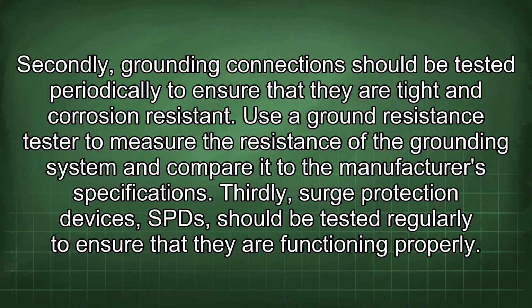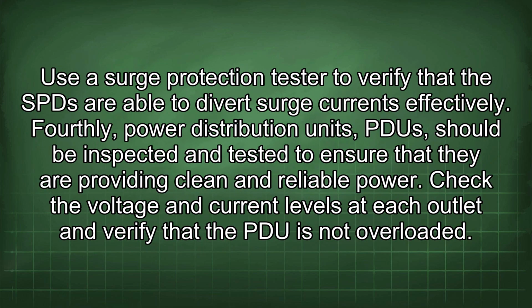Secondly, grounding connections should be tested periodically to ensure that they are tight and corrosion resistant. Use a ground resistance tester to measure the resistance of the grounding system and compare it to the manufacturer's specifications. Thirdly, surge protection devices, SPDs, should be tested regularly to ensure that they are functioning properly. Use a surge protection tester to verify that the SPDs are able to divert surge currents effectively.